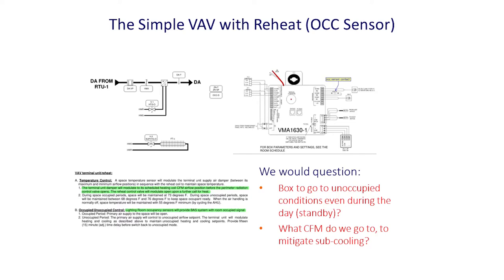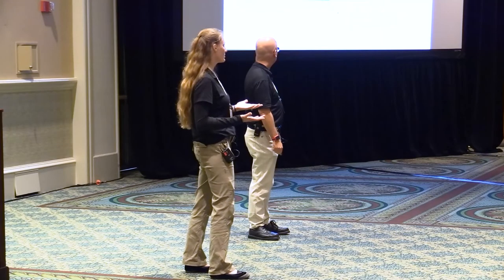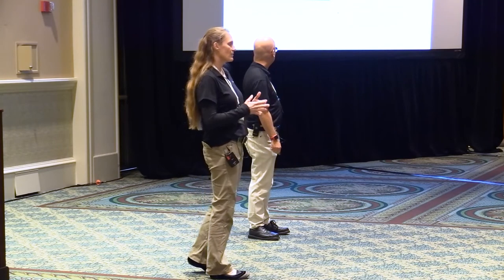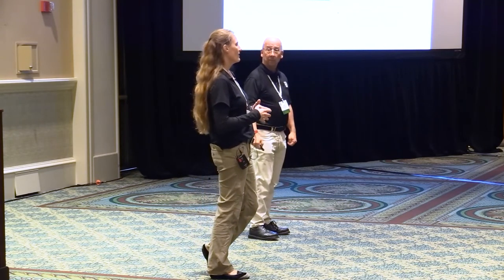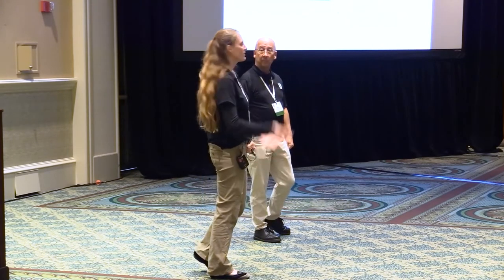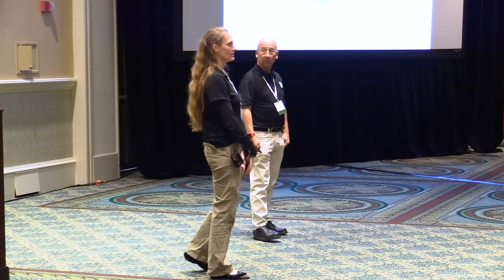Occupied, unoccupied, standby. We need to understand whether we're talking about unoccupied during occupied hours, where we just go into standby because someone left the room for a while, or unoccupied because the building is unoccupied from a scheduled perspective. Those can have different extended set points, whether from a temperature or an airflow standpoint.